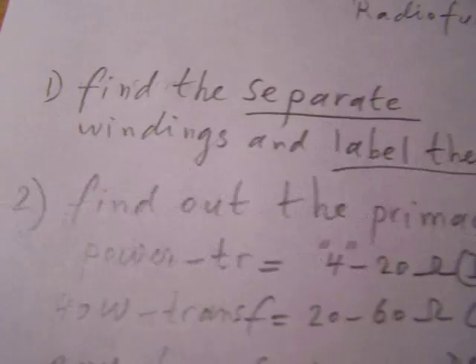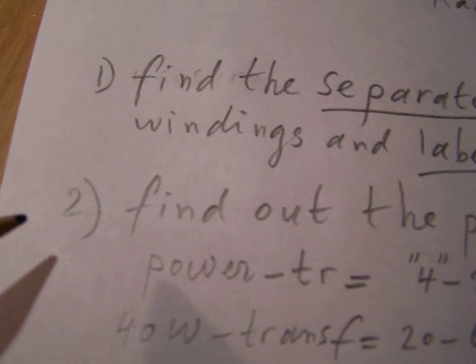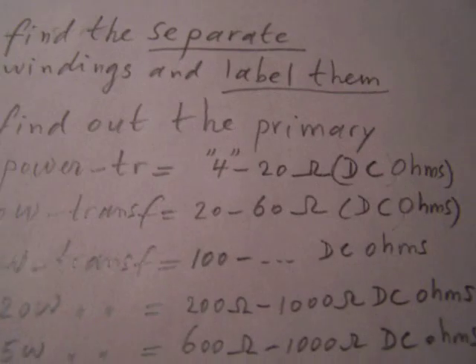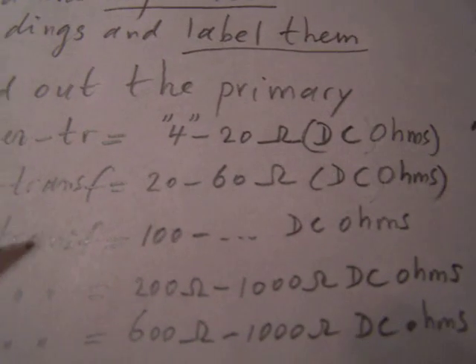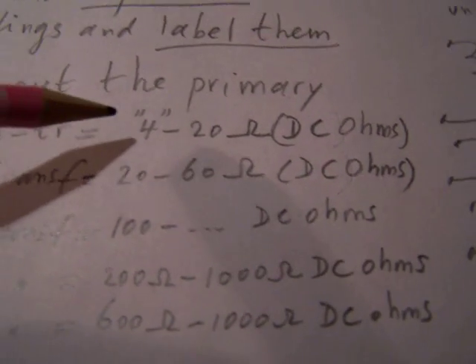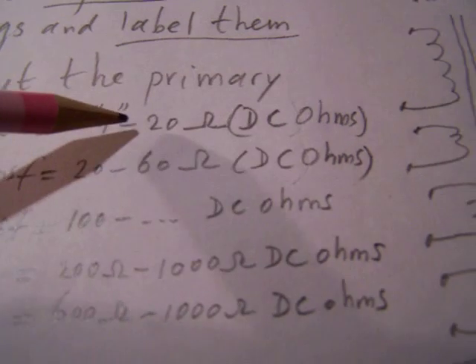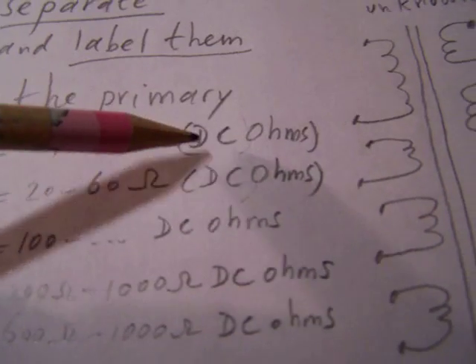Okay, find out the primary, that was point two. For power transformers, you can use this rule of thumb that 4 ohms up to 20 ohms DC resistance for the primary coil is normal.